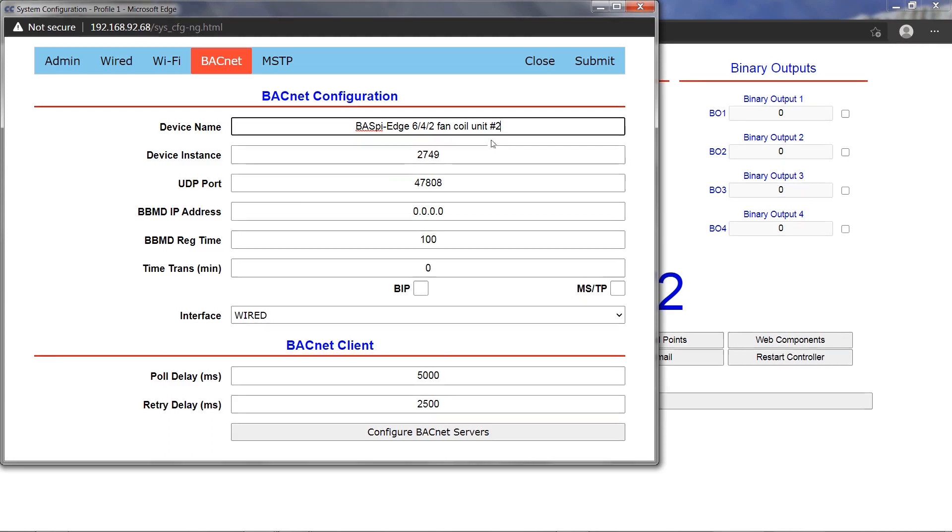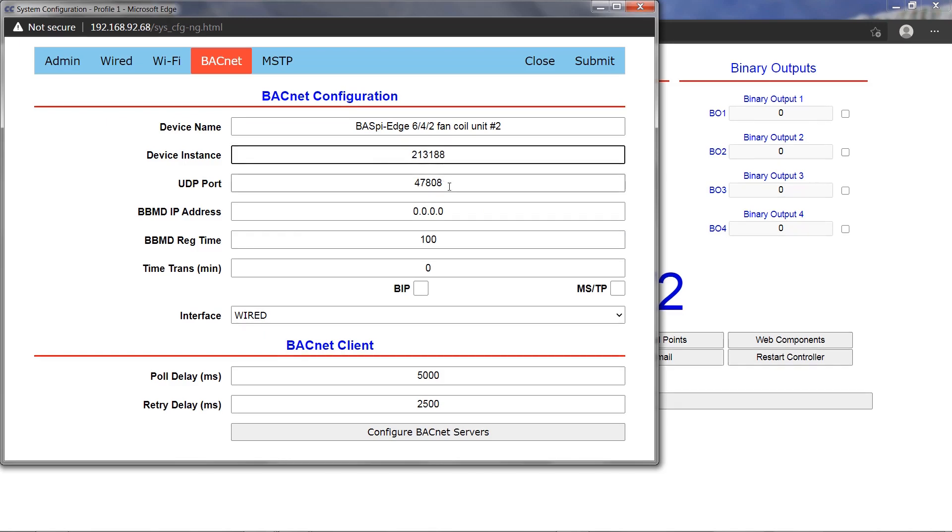The default UDP port of 47808 could be changed if needed. If the BACnet device needs to register as a foreign device to a BBMD, the BBMD IP address and registration time can be configured here.